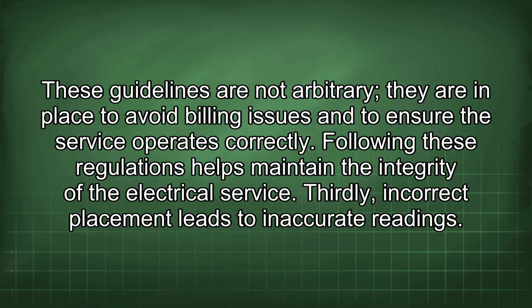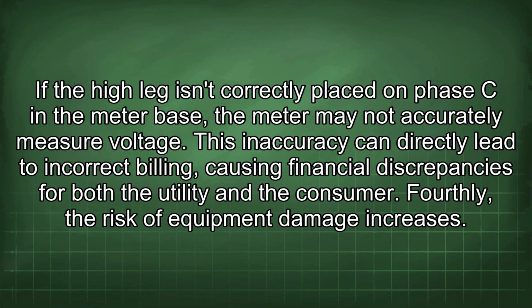Thirdly, incorrect placement leads to inaccurate readings. If the high leg isn't correctly placed on phase C in the meter base, the meter may not accurately measure voltage. This inaccuracy can directly lead to incorrect billing, causing financial discrepancies for both the utility and the consumer.